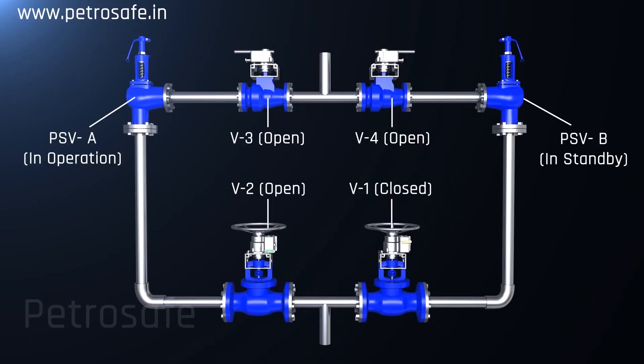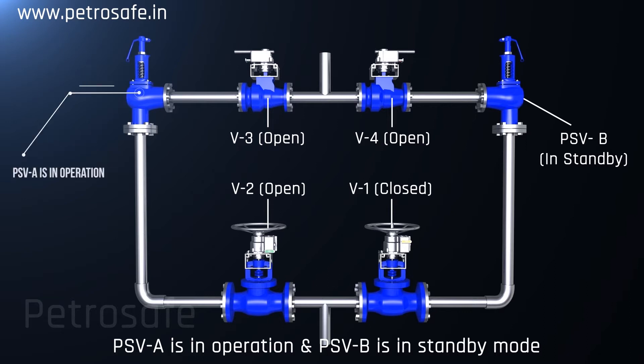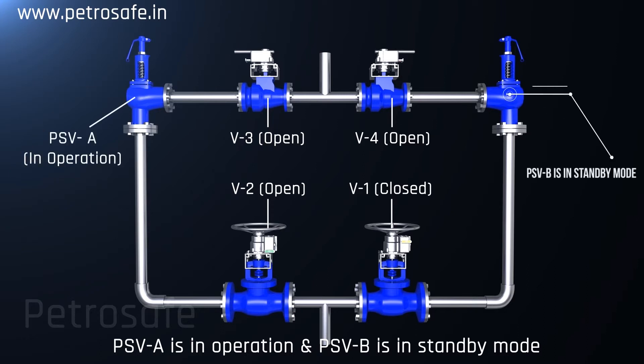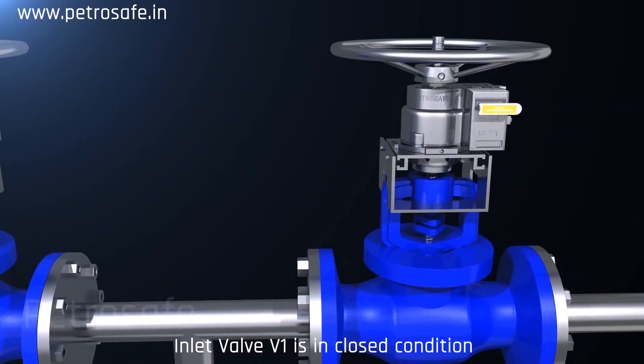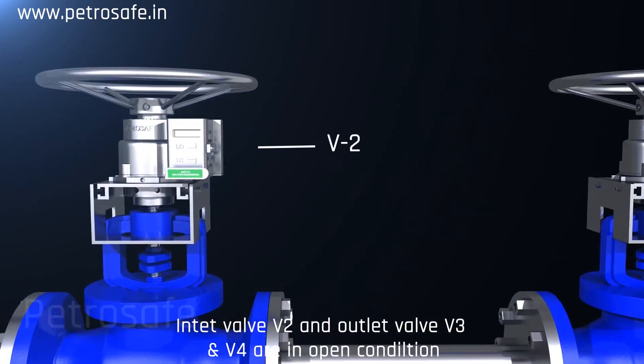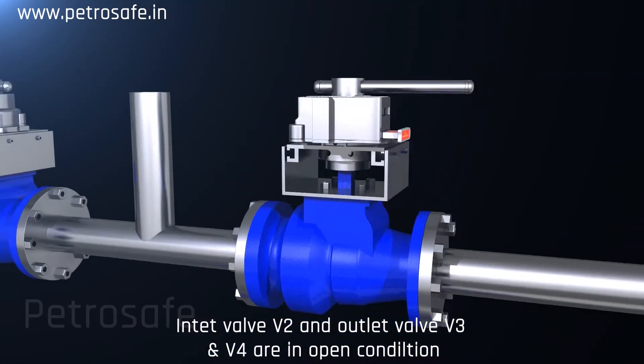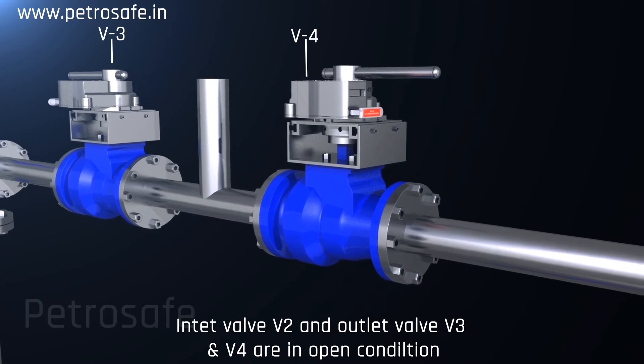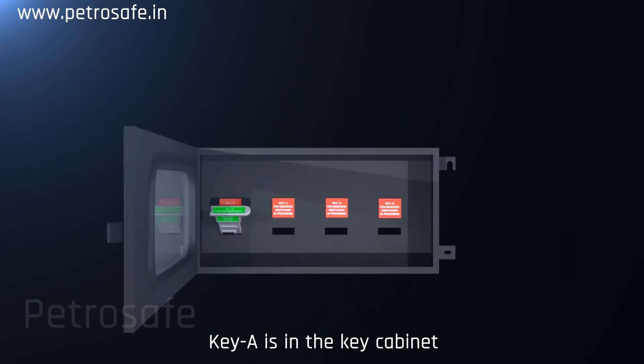Let us see the safe operation of a PSV using a valve interlocking system with a predetermined sequence. The current situation is as follows: PSV A is in operation and PSV B is in standby mode. Inlet valve V1 is in closed condition. Inlet valve V2 and outlet valves V3 and V4 are in open condition. Key A is in the key cabinet.